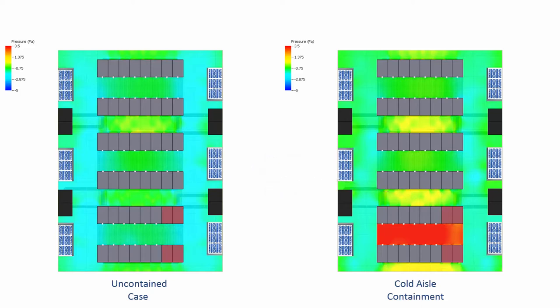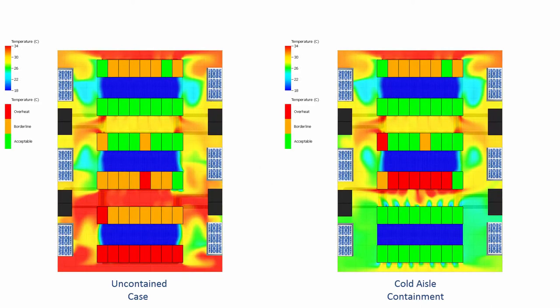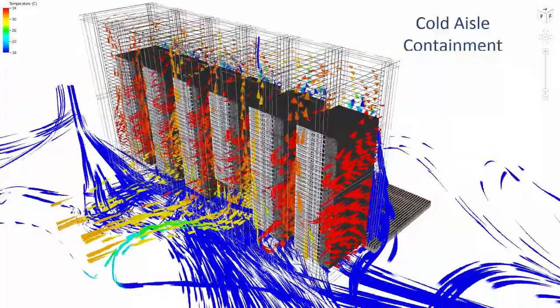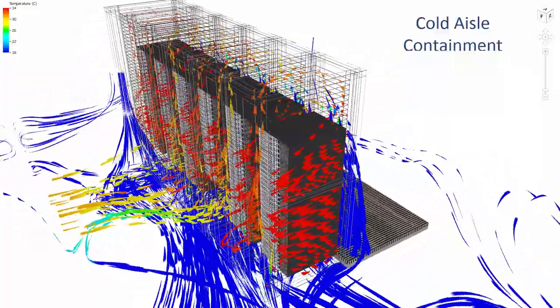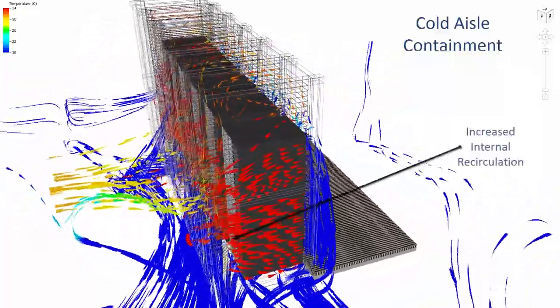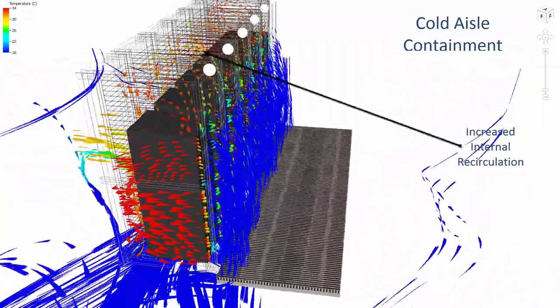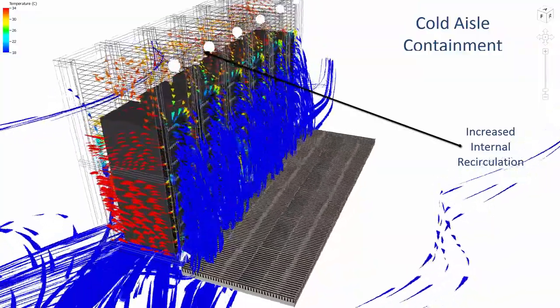As a result, exhaust air is pushed back into the adjacent aisles, thereby increasing the internal recirculation within the cabinets. Recirculating exhaust air travels towards the equipment inlets, thereby increasing the inlet air temperature. The combination of these issues mean that the cooling capacity of the air supplied to the central aisle has been reduced. A possible solution for the thermal issues in the contained case could be to introduce blanking inside the cabinets. This will prevent the internal recirculating flow from returning to the equipment inlets.